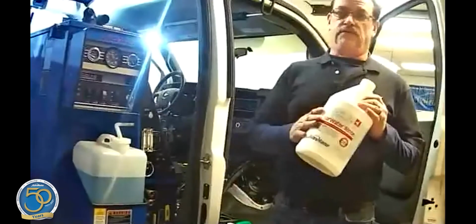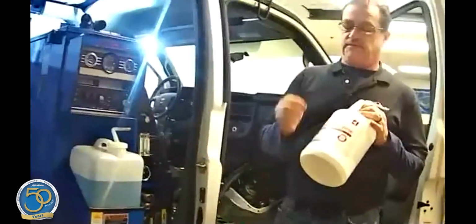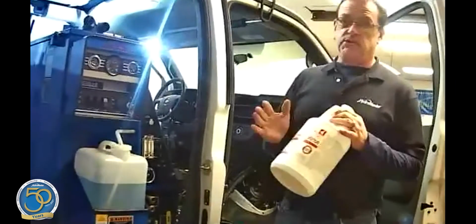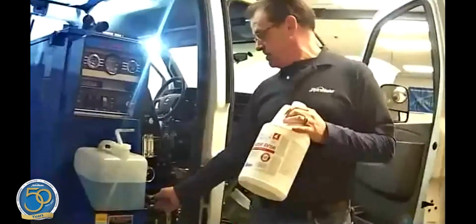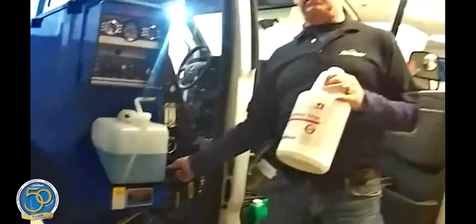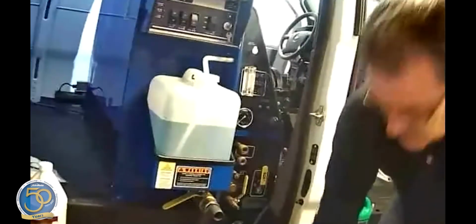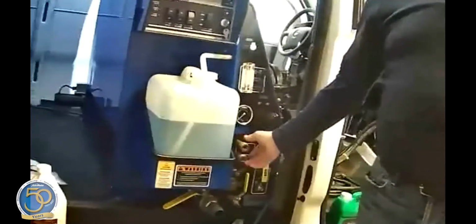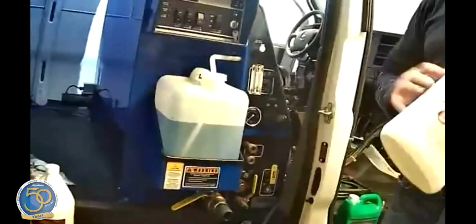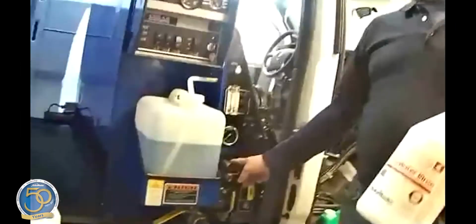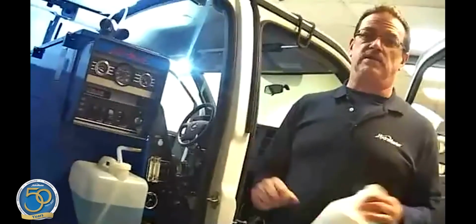Run it 10 minutes, dwell it 10 minutes, then flush it out thoroughly. This will break stuff free and it will come out in chunks of deposits. To get the machine clean internally, you'll most likely want to open flow one of the quick connects real quick. What I mean is you take a quick connect end off and just open flow it, because otherwise you'll push all that stuff through your hoses. You want to open flow the quick connect when you're done so it flushes out the chip formations instead of them building up behind the quick connect. A lot of times that requires pulling the quick connect off, depending on how much buildup you had.